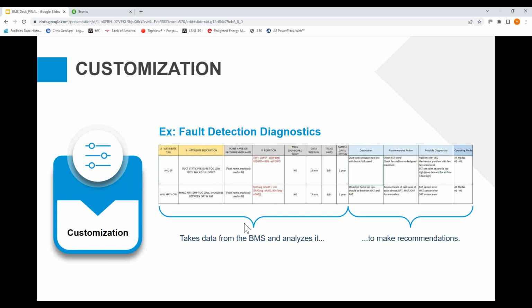And then when those conditions are met, it's going to tell you three different things. First, a description of what the issue is: the mixed air temperature is too low. That value of that sensor should be between the outside air temperature and the return air temperature. And then it goes even further to tell you recommended actions.